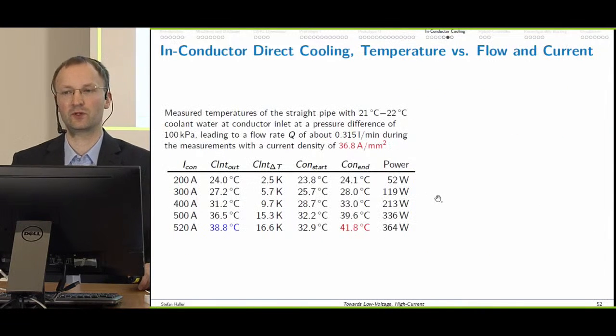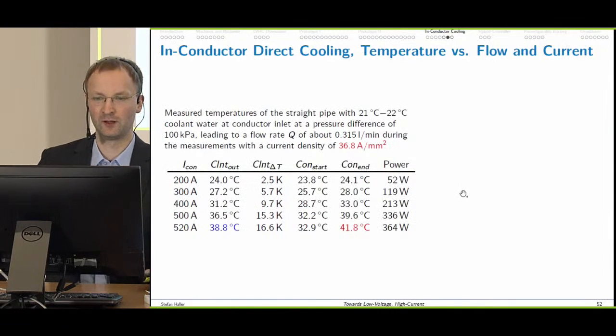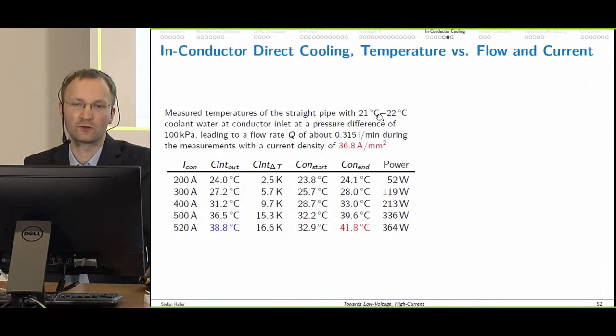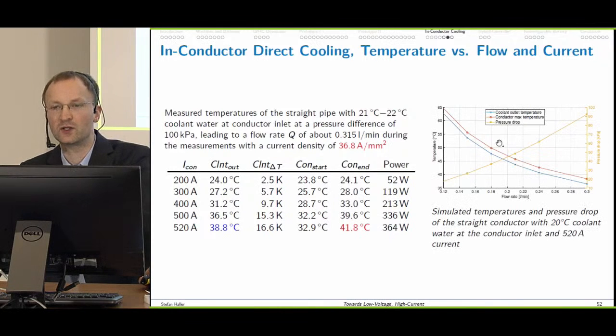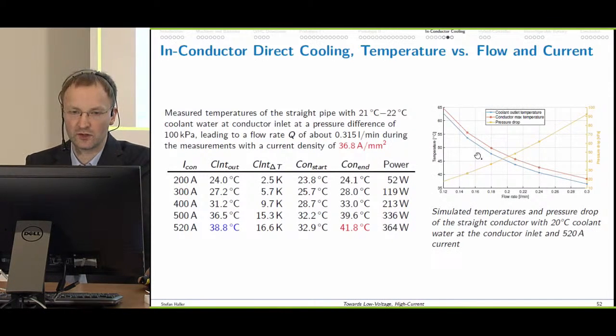What we see here is temperature versus flow rate and current. So if we have about 21 to 22 degree coolant at the inlet, a pressure drop of 100 kilopascal, resulting in a flow rate slightly above 0.3 liters per minute. And then we ramped up the conductor current and measured the adjacent temperatures here. Here on the right is the simulation of the same conditions.